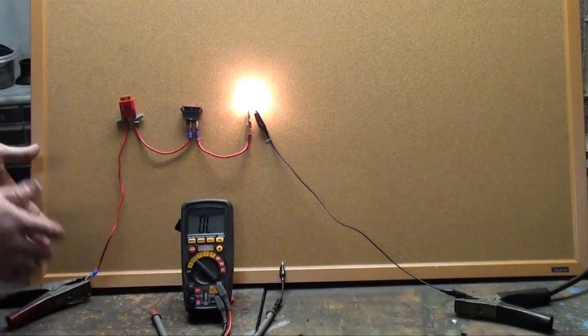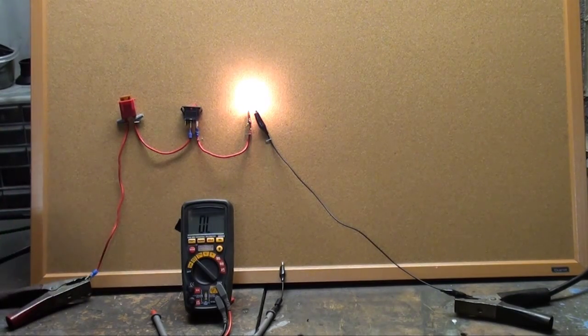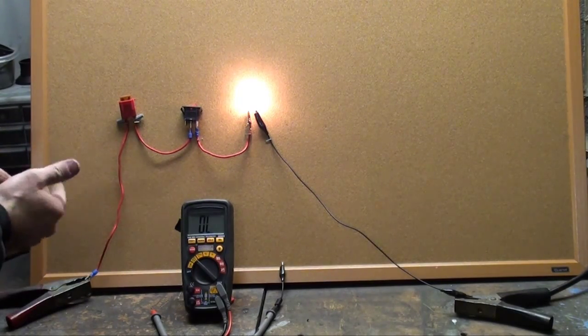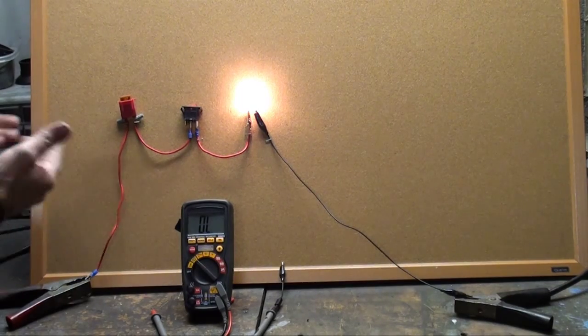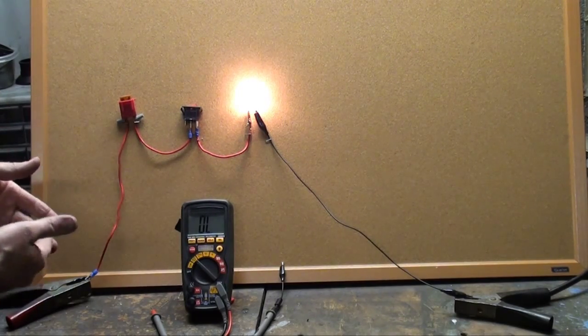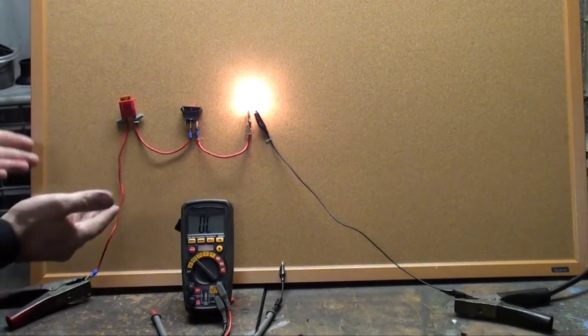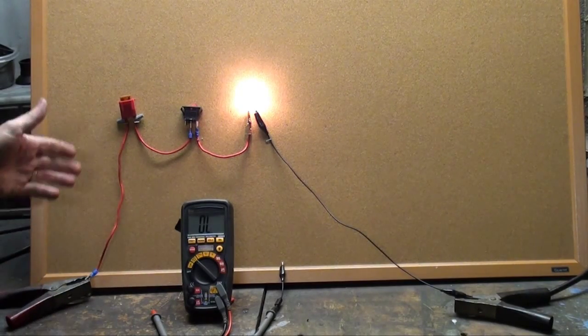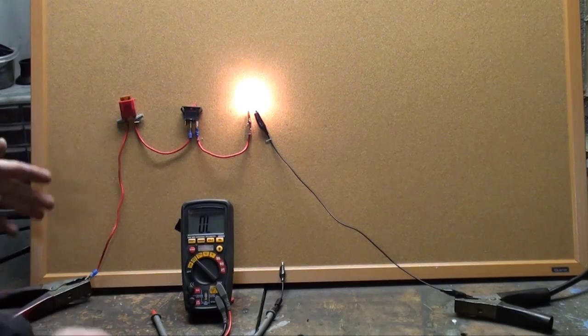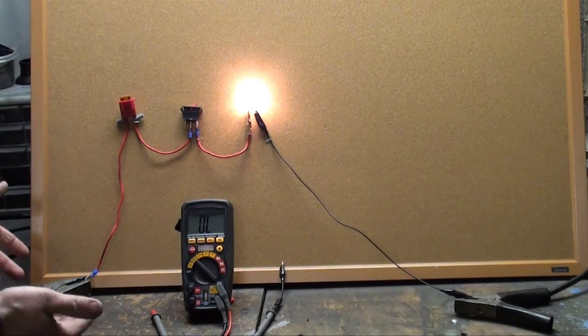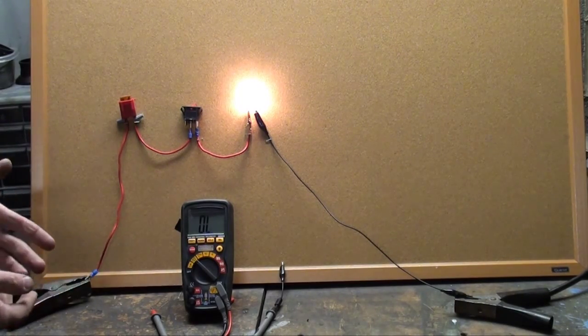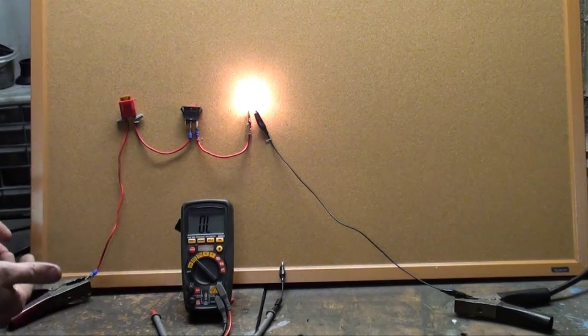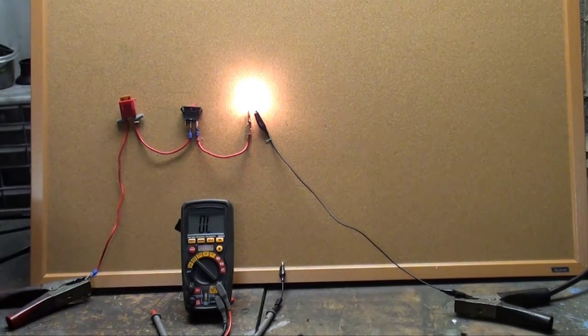So that's how you do basic troubleshooting using a DVOM. That's how I perform a voltage check to find the opening in the circuit, and that's how I also perform a continuity check. But remember, to do a continuity check, or to find the resistance in the circuit, make sure it's powered down first and the circuit's open, and then you can do your basic checks like I showed you.